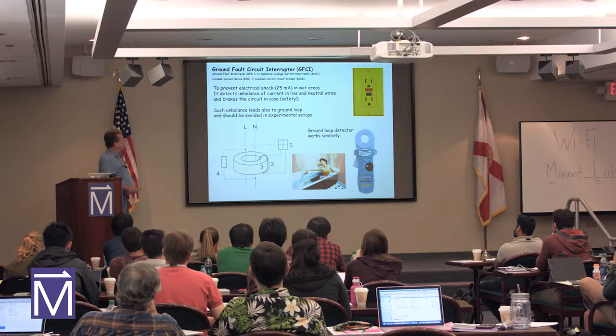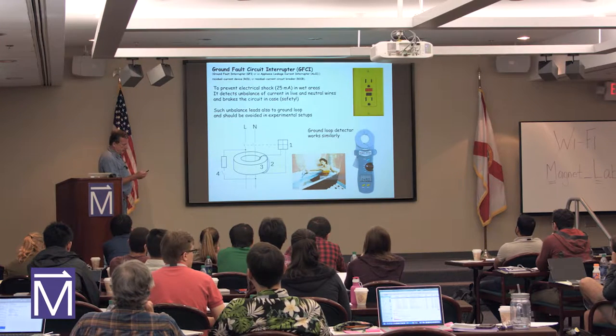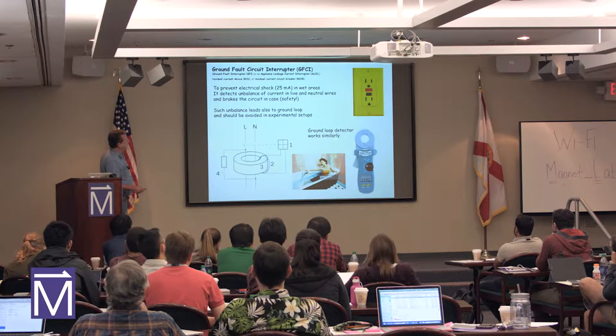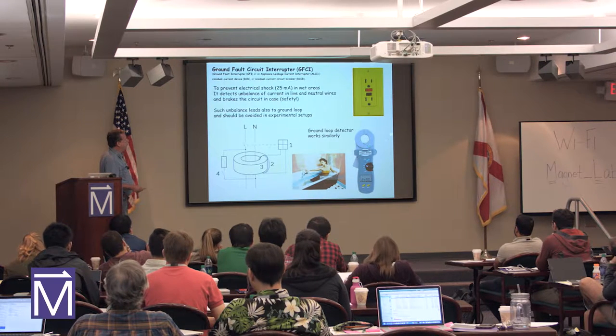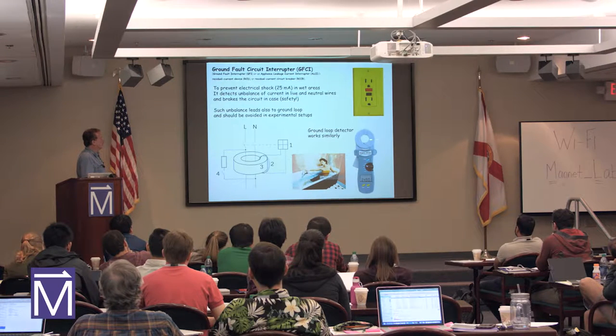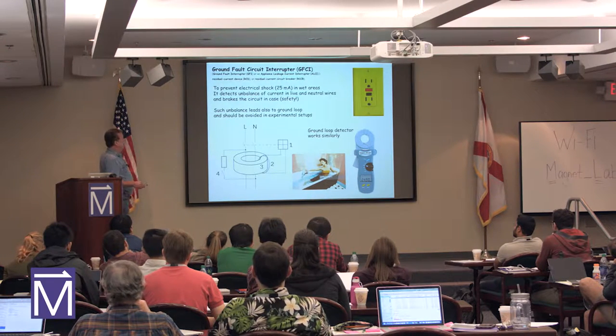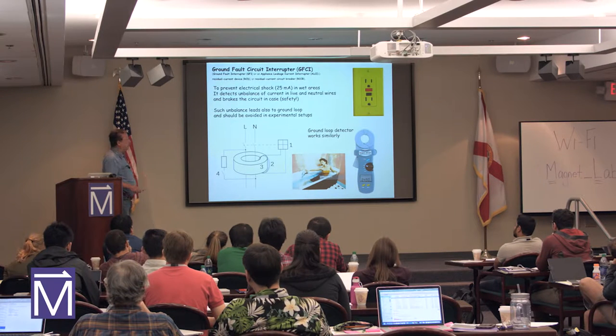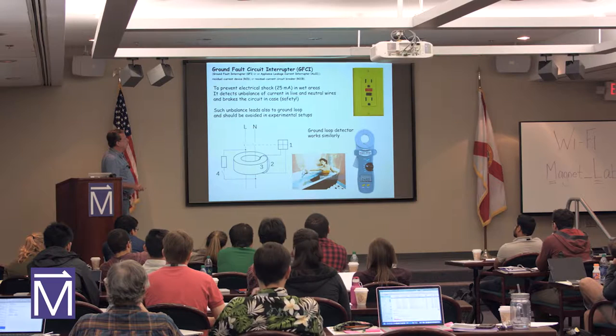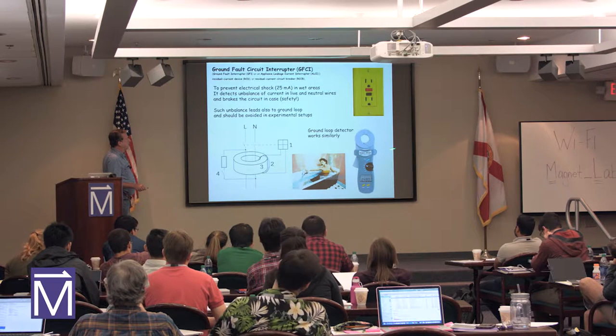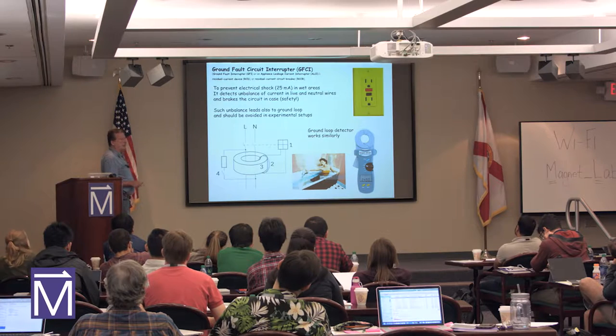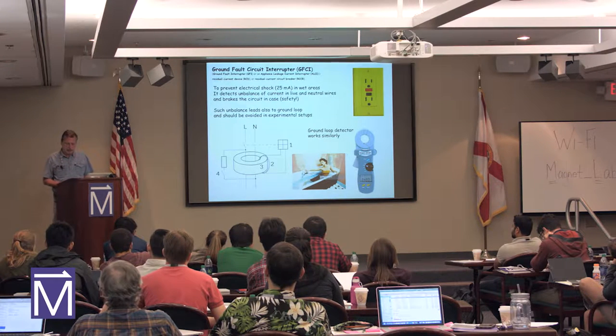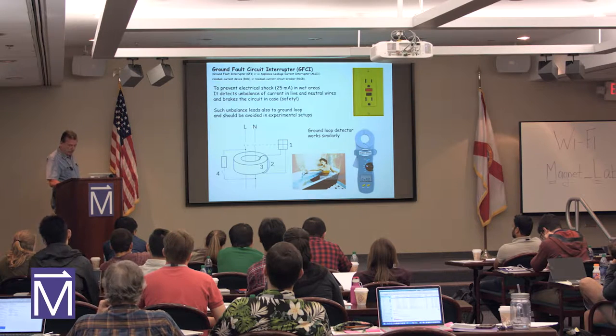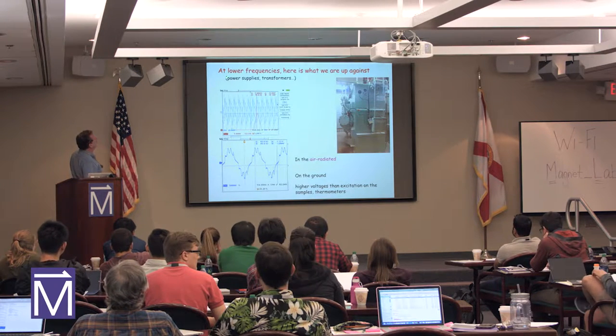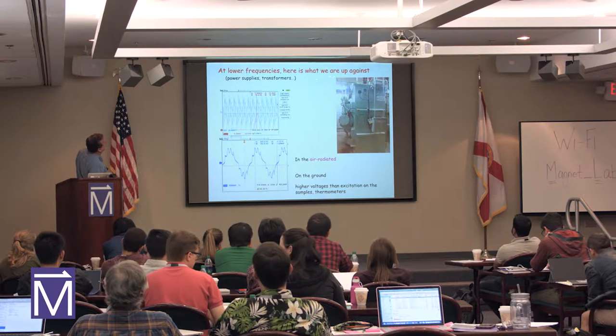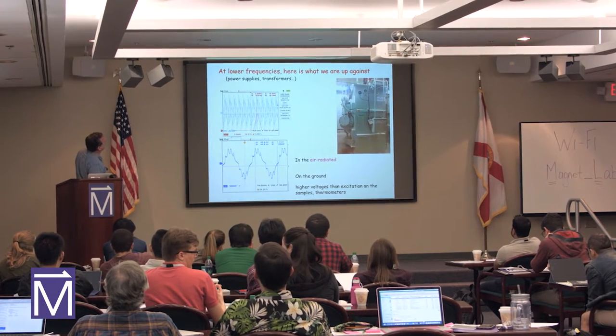Inside, on their outlet. Okay, our ground loop detector works very similarly. We have this clamp, and if any current goes inside this clamp, it's calibrated and shows this current. It is sort of a transformer with an open core, and the wire under investigation is just the secondary winding of the transformer. This is what we are up against in the lab at low frequencies.